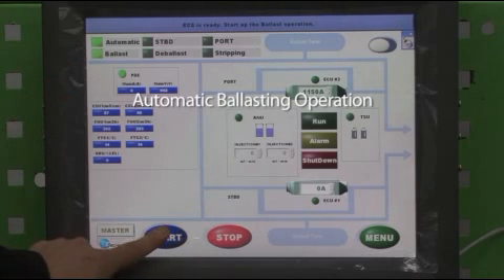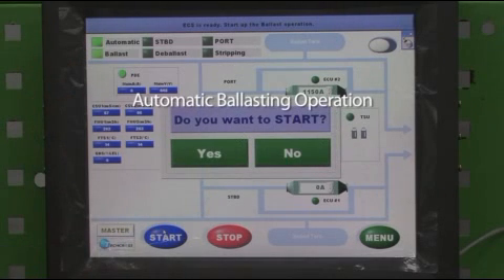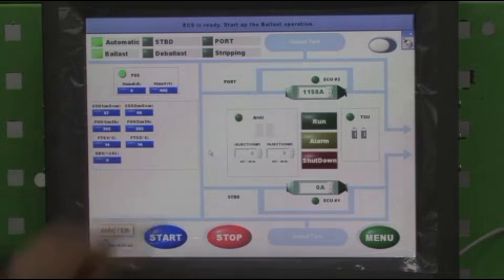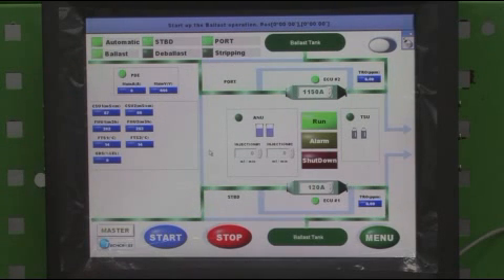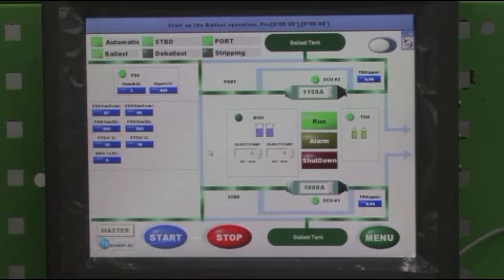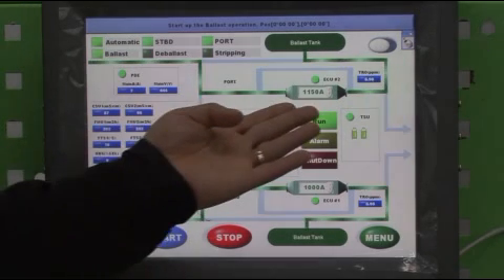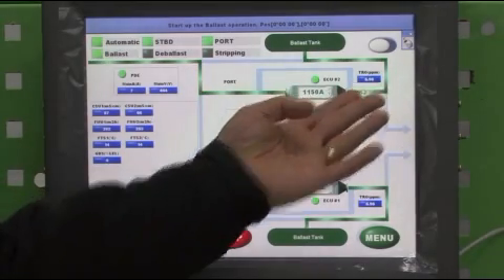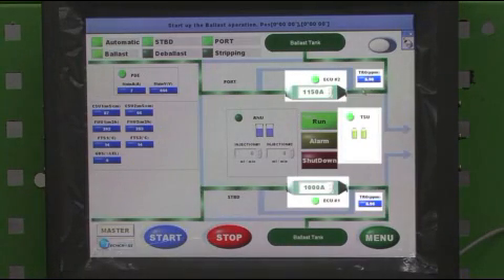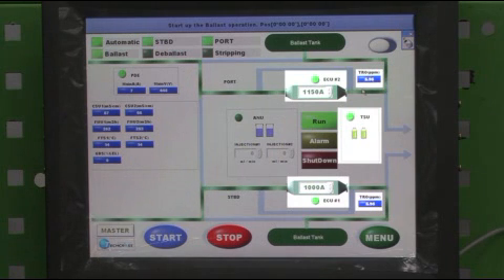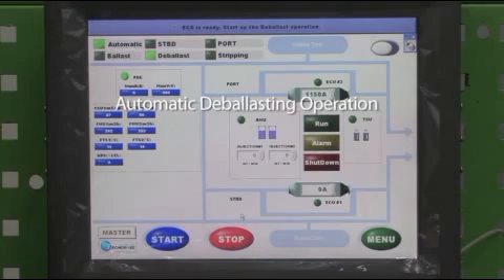Start up the ballast operation. Step 3. Click the Start button on the HMI screen to start ECS. Step 4. Ensure that the ECU value and TRO value are displayed within 5 minutes after starting ECS. Alarm or shutdown should not occur during normal operation. 4. Automatic deballasting operation.